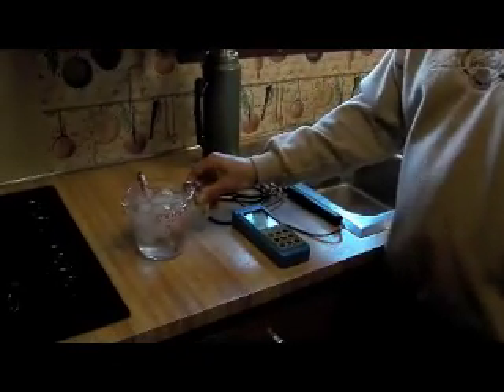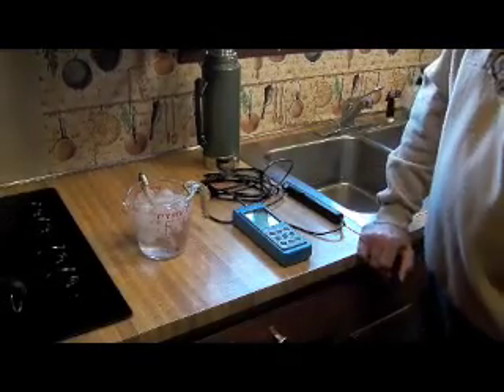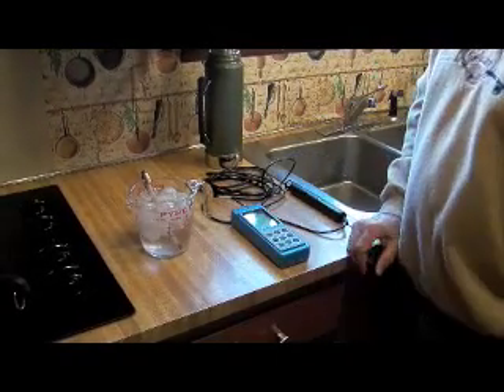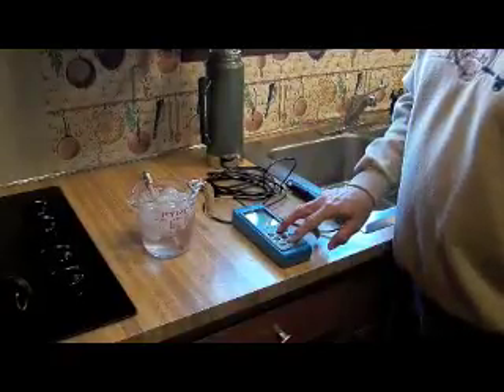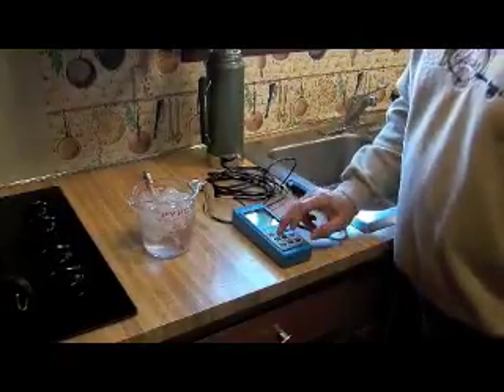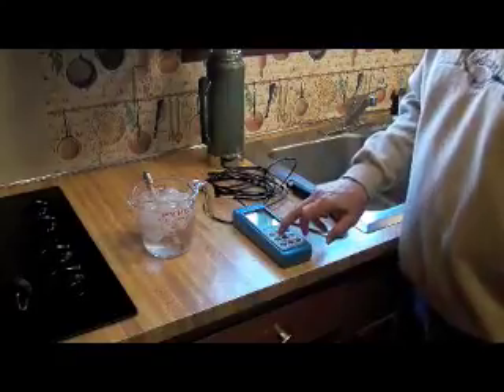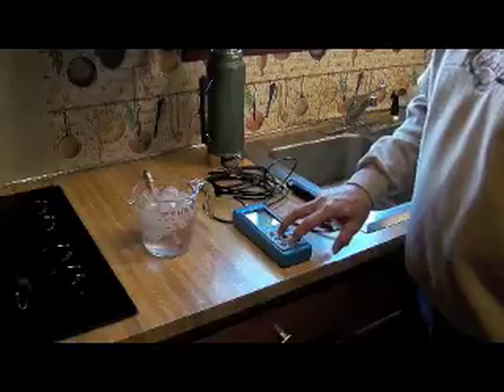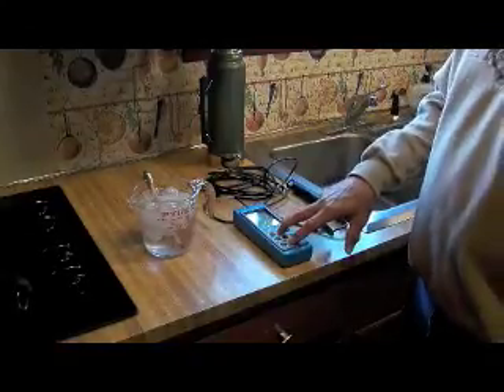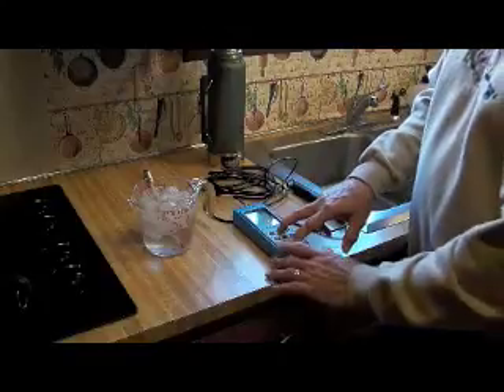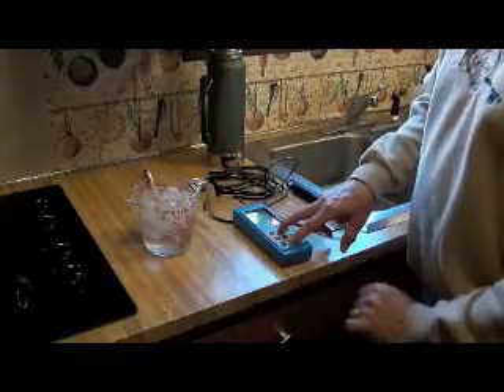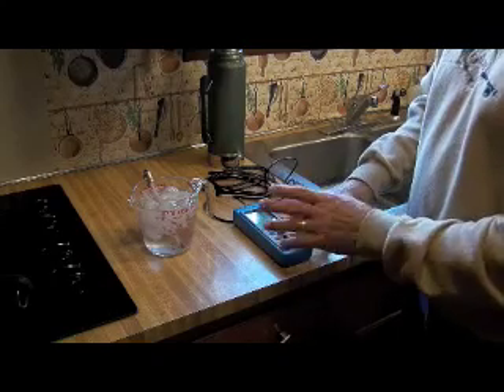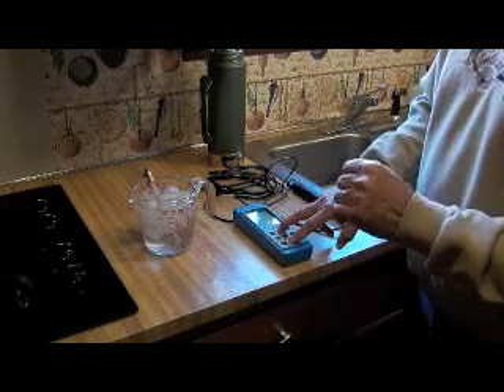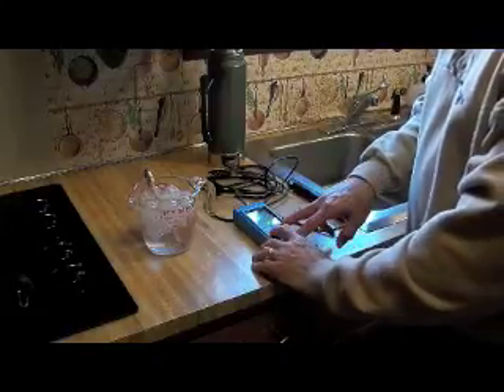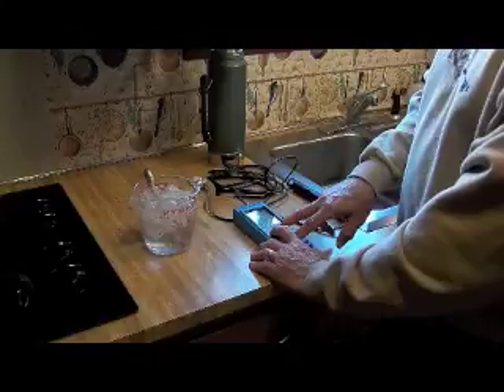Okay, we're doing the temperature calibration. I have my ice water slurry here sitting close to 0 degrees C, and I've got the meter off. And the instructions say that you need to simultaneously push the range button on the center top simultaneously with the down arrow button, 2 buttons below that, and then turn the unit on while holding those buttons down. And just hold everything down for, it seems like it needs to be at least 3 seconds.